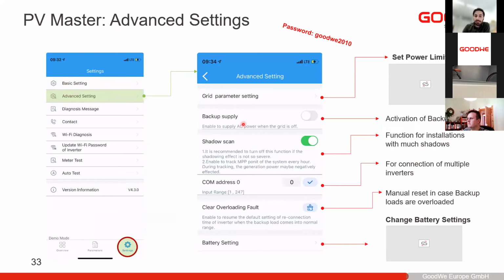Under advanced settings, you can change the grid parameters manually. In case you have very specific grid parameters you need, you set up the basic ones, and afterwards you can change the grid parameters to suit you. In case you want to use the backup output, you need to activate it here as well. So you have the backup supply here, you just activate this one.